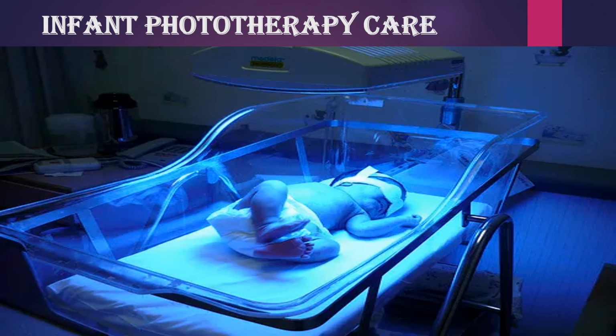Next is infant phototherapy care. This is an important procedure which was asked in JIPMER 2023 skill test. First, you have to check whether the phototherapy light is properly functioning or not. Second, no clothes or any other objects kept on the phototherapy machine.